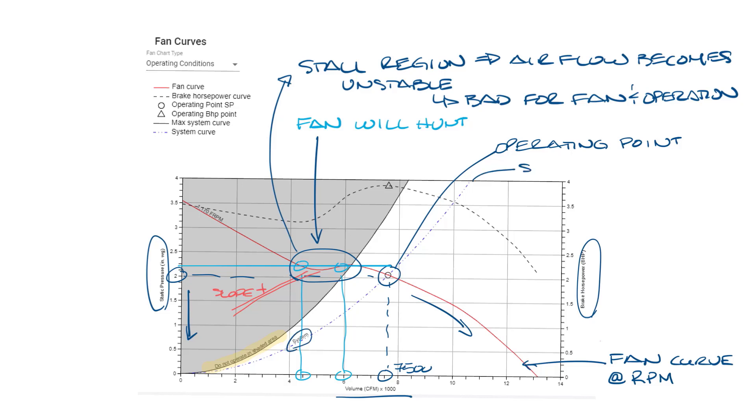This dotted line is the system curve. The system curve is a representation of your system. It's the ductwork and whatever else you need to move the air against. It's important to know that if you change your system, like adding a bunch of extra ductwork or closing off dampers, this changes the system curve and will affect your fan's performance. Changes in your system can shift the system curve left or right.